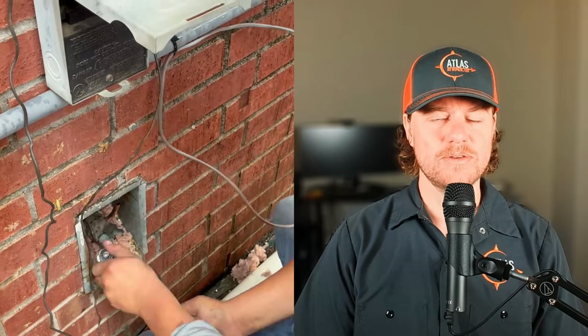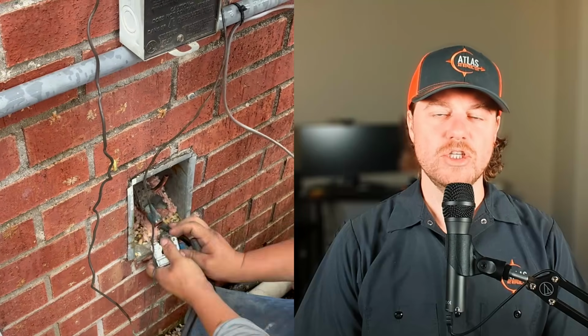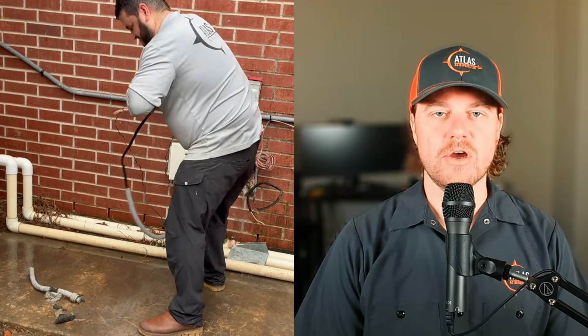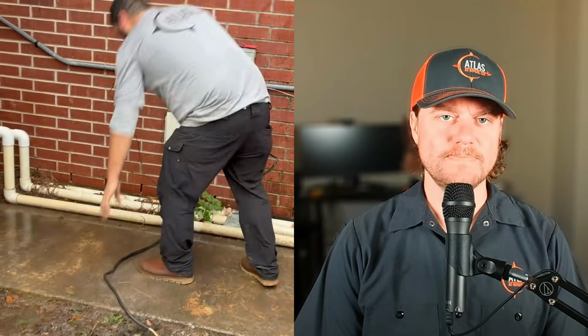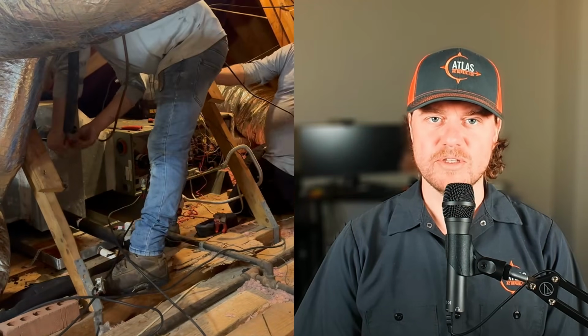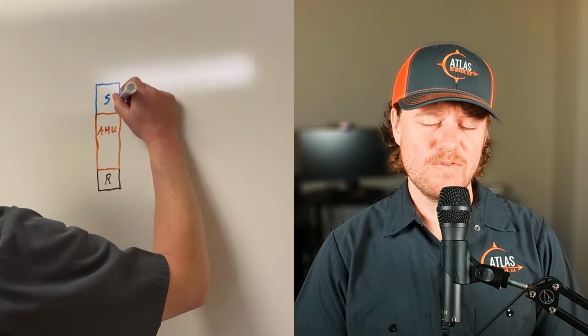The Carrier Infinity is arguably the best system on the market for zoning. You can daisy chain 2 control boards together and get up to 8 zones. However, there are some limitations to it, and a lot of times you can only get away with 4 zones. That's because there's a problem that a lot of people get wrong whenever they install one of these zoning systems, and that is using the correct amount of airflow per zone.